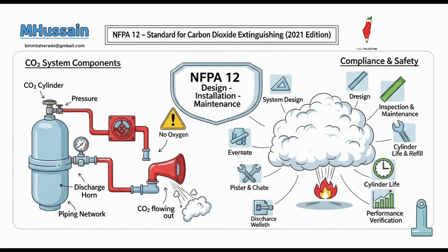Knowing CO2's strengths, what are its specific weaknesses? The standard is incredibly clear here. Okay. CO2 is explicitly not effective and should not be used for fires involving certain types of materials. This includes chemicals that contain their own oxygen supply, like cellulose nitrate. Right, things that burn without air. Exactly. They can burn even in the absence of atmospheric oxygen. It also applies to reactive metals such as sodium, potassium, magnesium, titanium, and zirconium, as well as metal hydrides.